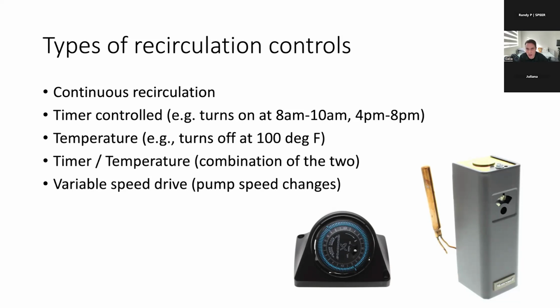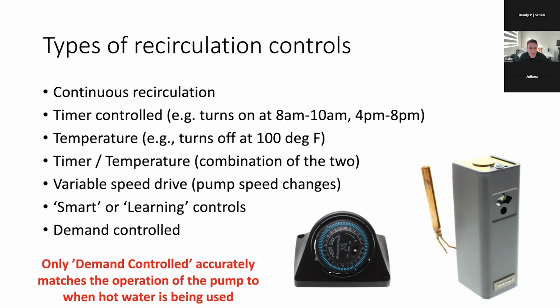VSDs started off on the hydronic side and closed loop systems, and then they've sort of meandered over into the domestic hot water side of things. So we're starting to see a lot more of those systems on the market. We see some new controls that supposedly learn your habits, and they operate the pump based on some type of algorithm where it looks at your habits from the week before. Now, the problem with these types of controls, and I think we can all think about our own hot water use on a day-to-day basis, is that oftentimes those hot water events are completely spontaneous and therefore unpredictable. Okay. So it's very hard, if not impossible, to know exactly when you're going to use hot water. And then last but not least, there's demand control, and only demand control accurately matches the operation of the pump to when hot water is being used.